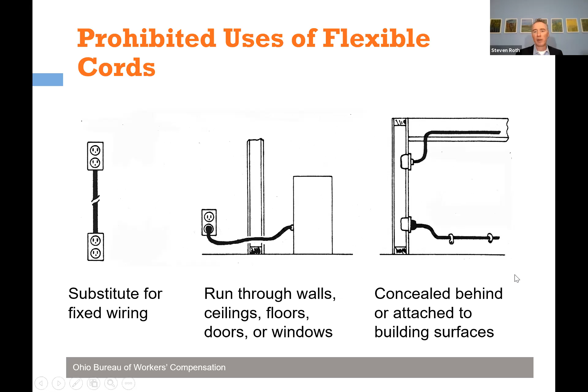All extension cords we use have to be a 3-wire type. They have to have that grounding conductor, and they have to be marked for either hard or extra hard usage. You're never going to see those actual words on your cord sets though. You'll see, as in the diagram, SJ, which is for hard, or just S, which is extra hard, and the J stands for junior service. It's weird nomenclature, but SJ or S is what you're looking for on all your cord sets. If you don't have that, you don't want to be using it.